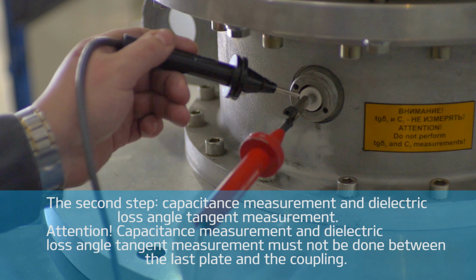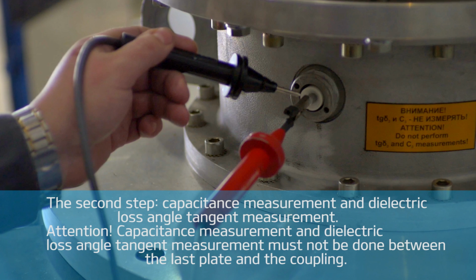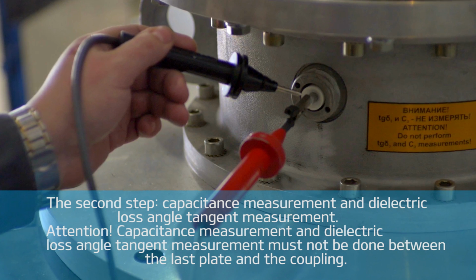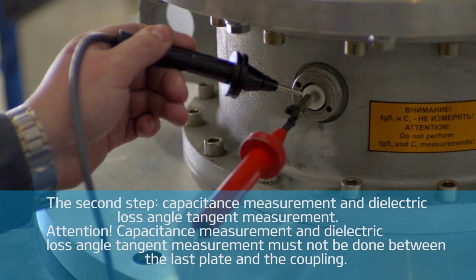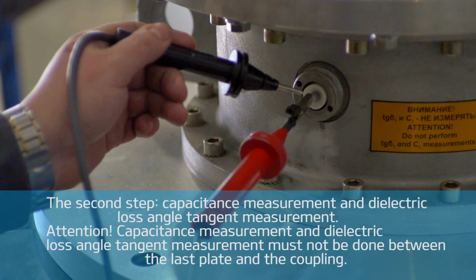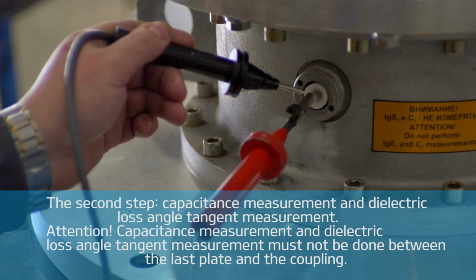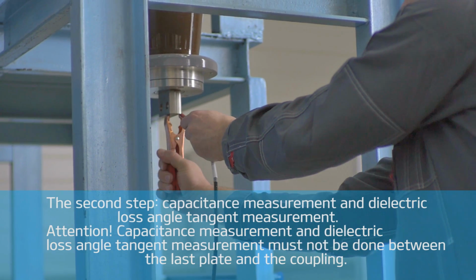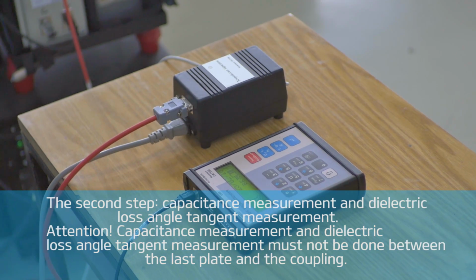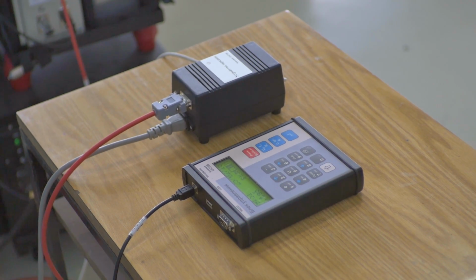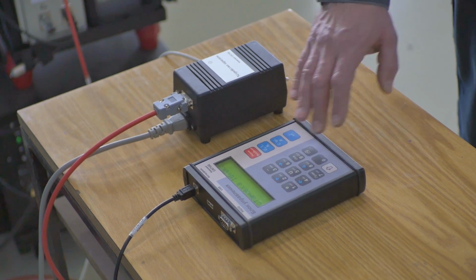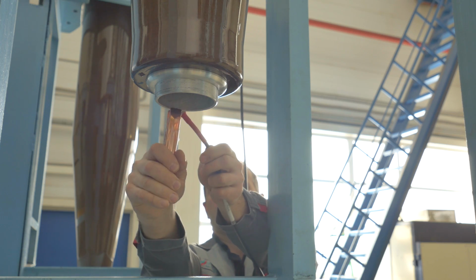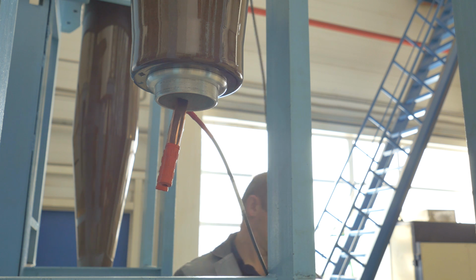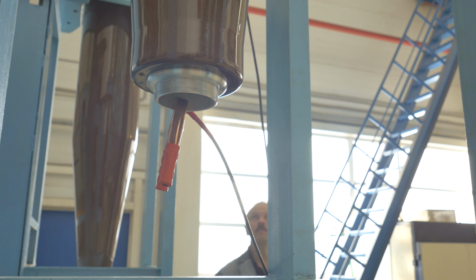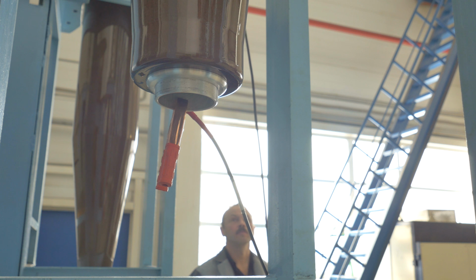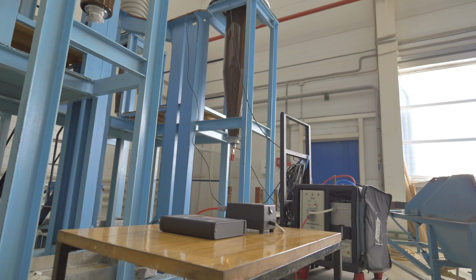Attention! Capacitance measurement and dielectric loss angle tangent measurement must not be done between the last plate and the coupling, because the applied voltage can cause electrical damage of the test tap unit. Bushing checks require a certain experience with tools, measurements and configuration, and results interpretation. Partially, it depends on the fact that capacitance values are relatively small and can be distorted even by spatial factors of the ambient, including a bushing's position inside a transformer, that can influence measurement value after installation.